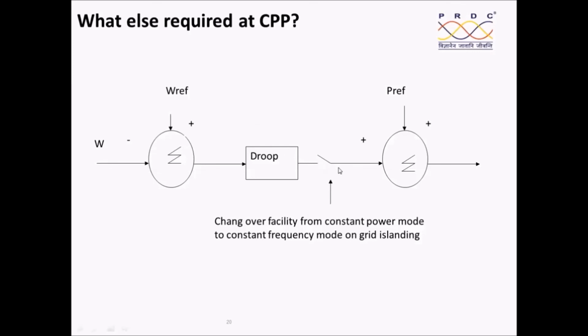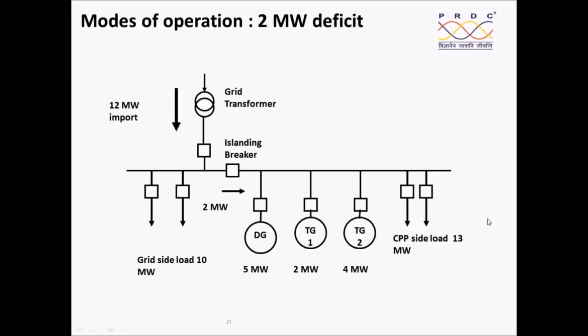Therefore, there is one islanding breaker. As soon as the islanding breaker operates, the signal of that should be taken, so that it is possible to ensure that from the constant power mode, I am going to the constant frequency mode of operation. That is possible provided the islanding breaker signal is taken for our governor control action. There can be different modes. I have just taken this example to give an illustration for a very small system. Afterwards, we'll try to look into a large system.